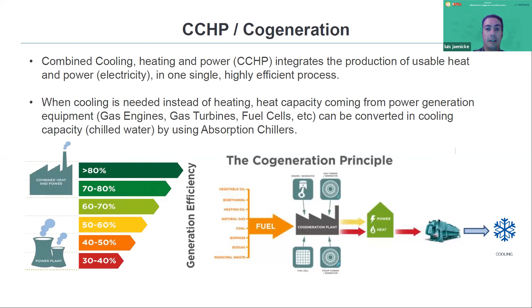So why are absorption chillers a good match for cogeneration? Essentially, and this is the most important thing, because absorption chillers are driven by waste heat. So if I replace the mechanical chillers in a traditional data center design with absorption chillers, I am no longer consuming most of the electricity that would go to the chiller plant within the data center, and I'm recovering all this heat that otherwise would be released or not used. Another very important point is the refrigerant they use. In a traditional data center design with mechanical chillers, these chillers normally use HFC or HFO refrigerants that contribute to global warming when released to the ambient. But absorption chillers use water as refrigerant. It's one of the few natural refrigerants in the market, together with ammonia or some hydrocarbons.